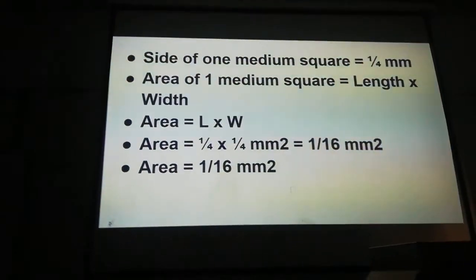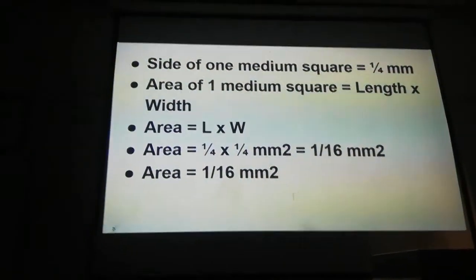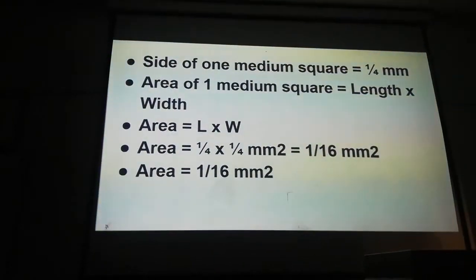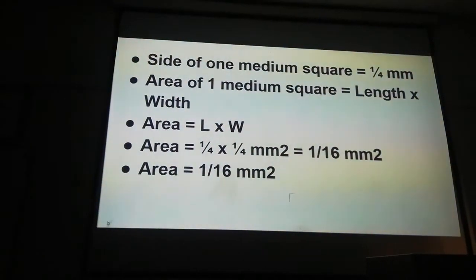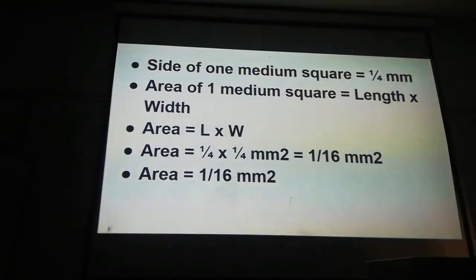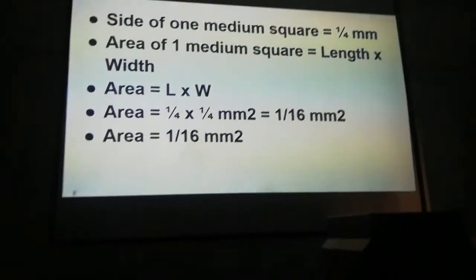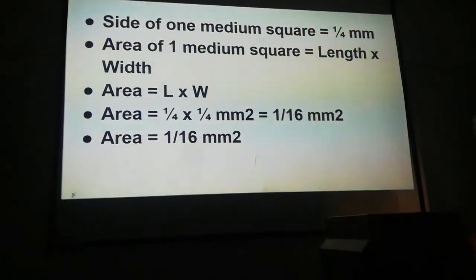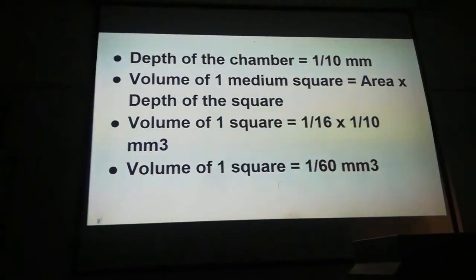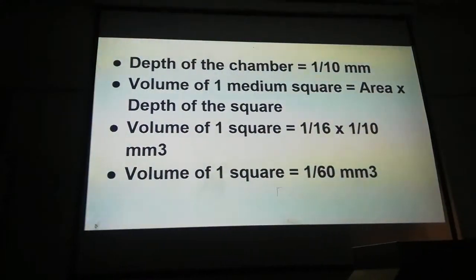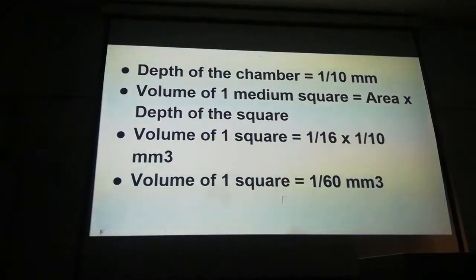Since both length and width of the medium square are 1/4th of a millimeter, multiplying 1/4 × 1/4 gives an area of 1/16 mm². The area of 1 medium square is 1/16 mm². The depth of the Neubauer chamber is 1/10 mm — this is constant, as it is how the chamber is made.